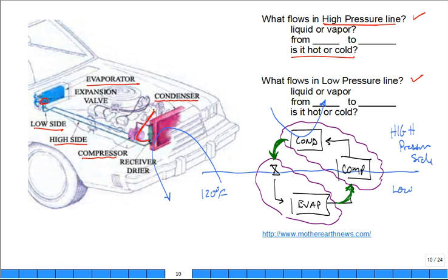And then if you're on pavement, parking lot, your engine's sitting there belching off a lot of heat too. The automobile radiator is right behind it. It can be very hot. You have to reject heat to that. So what's the temperature of the refrigerant in the condenser? A good 15, 20 degrees higher. Does that make sense? The refrigerant in here is, let's say, 145.